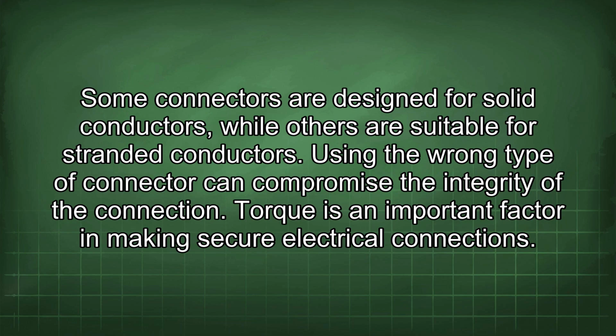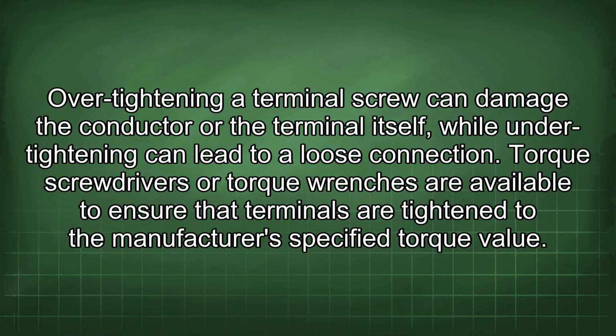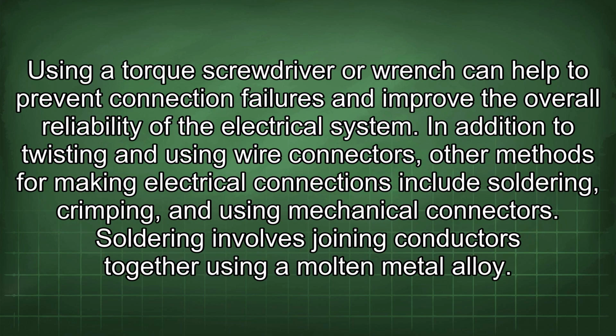Torque is an important factor in making secure electrical connections. Over-tightening a terminal screw can damage the conductor or the terminal itself, while under-tightening can lead to a loose connection. Torque screwdrivers or torque wrenches are available to ensure that terminals are tightened to the manufacturer's specified torque value. Using a torque screwdriver or wrench can help to prevent connection failures and improve the overall reliability of the electrical system.